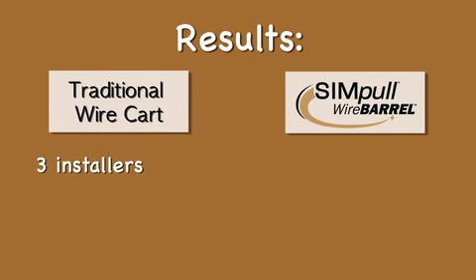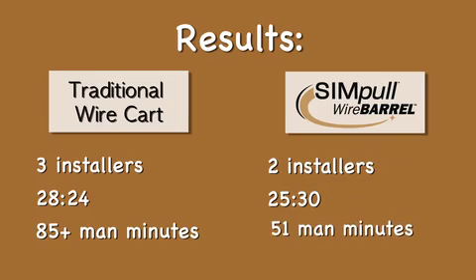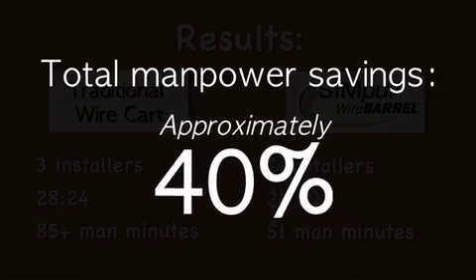In this scenario, three installers using the traditional wire cart method completed their pulls in 28 minutes and 24 seconds, a total of more than 85 man minutes. The two installers using the SIMpull WireBARREL system completed their pulls in 25 minutes 30 seconds, or an equivalency of 51 total man minutes. That's a total manpower savings of nearly 40%.